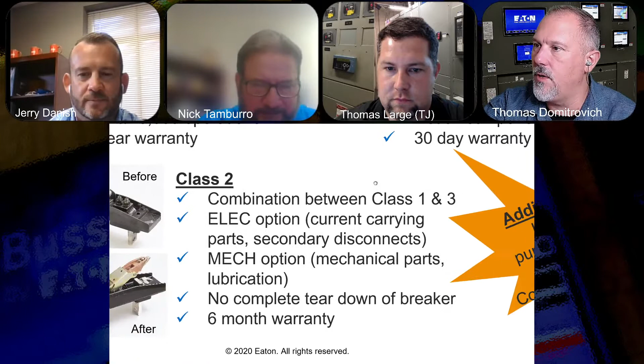Say a customer sends in a breaker for what we call a T&I, a test and inspect. They just want us to advise what level of reconditioning or repairs it needs. So the breaker frame is in really good shape, but the operating mechanism hasn't been serviced for years.